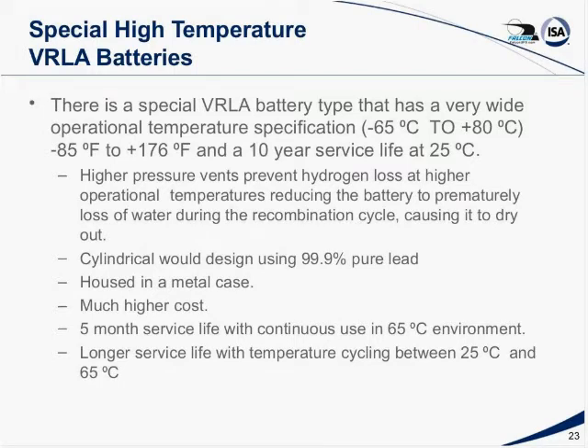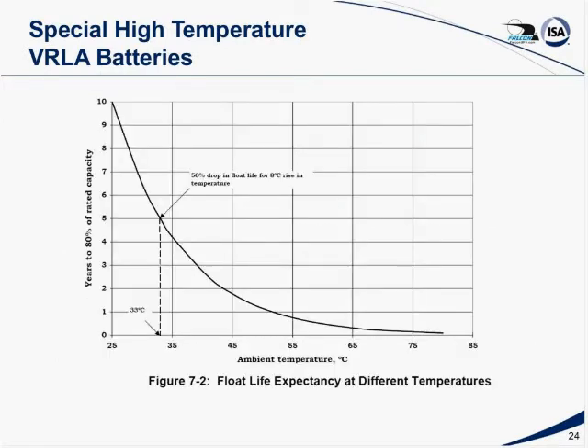At 65C, next slide, you'll see that they have about a 5-month service life. But again, if it's used in an outdoor application, that temperature is going to be cycling back and forth. But if it's used in an industrial application where it's a fixed 65C, it's about the only battery that's going to survive in that environment. And we can see here the battery manufacturer's float life expectancy on that battery: at 25C it's 10 years, at 65C it's a few months.